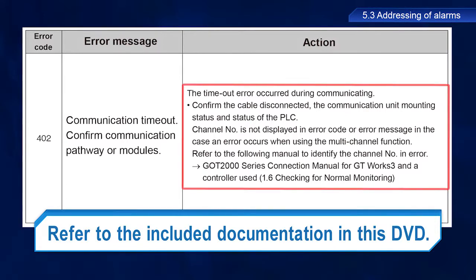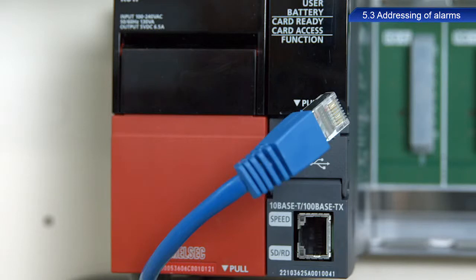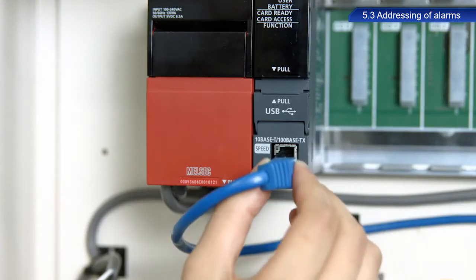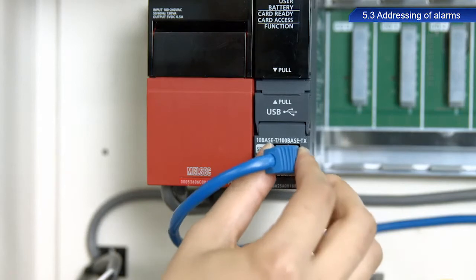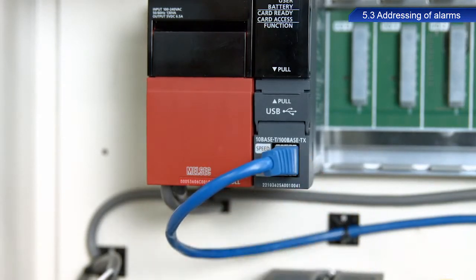As you can see, possible troubleshooting for the 402 error code is cable disconnected. So let's check the cable connecting the GOT and PLC. The cable was not connected correctly, which triggered the alarm. Reconnect the cable correctly. The cause of the error has been resolved.